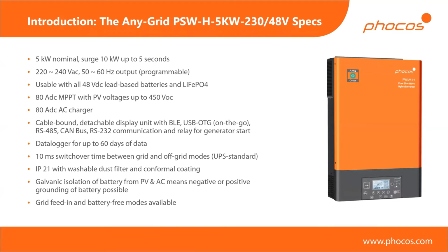So here we can handle 5 kilowatts. And we have a surge rating up to 10 kilowatts. So it means that even if you have difficult loads which take a large surge to start up, you have several seconds time with twice the nominal power to get those units started up. We have a programmable 220 to 240 volt AC output. So you can select 220, 230, 240 as the output, and you can select 50 or 60 hertz as the output frequency.